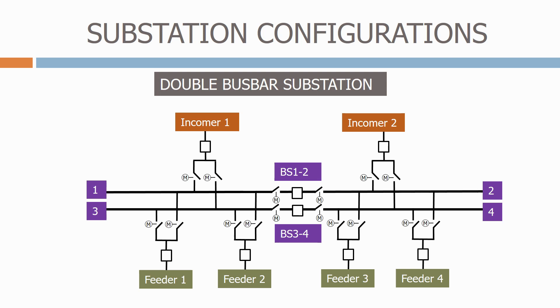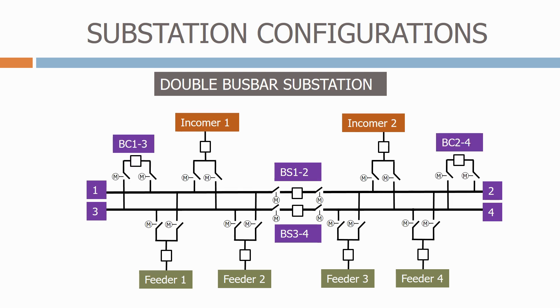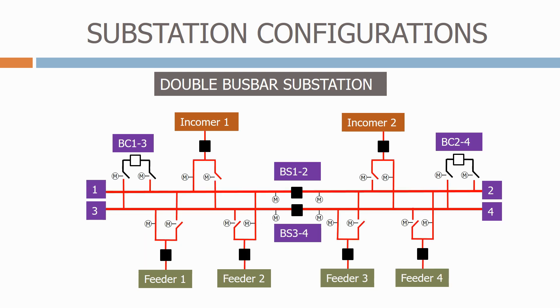Another popular configuration is a double bus bar station. This configuration provides multiple options for connecting the incomers and feeders together. In this arrangement we have four bus bars. Each of the incomers and feeders can be connected to one of two bus bars using the bus bar isolators. We can also add bus coupler circuit breakers to connect the upper and lower bus bars together. The normal configuration is for each incomer to feed two bus bars. One feature of this arrangement is that we can change which bus bar a feeder is connected to without disconnecting the load — this is done using what's called a on-load changeover sequence.